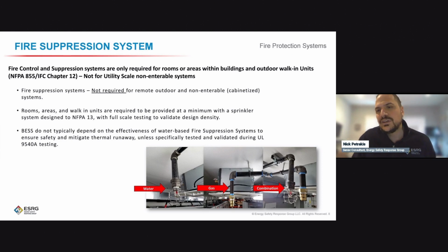Fire suppression systems really depend on where it's located. Indoor systems, walk-in units will require this mandatory, assuming this is in a building. Outdoor systems are more reliant on making sure that failure is contained within that enclosure and doesn't propagate, so they're not required to have external or water-based fire suppression systems. It really depends on fire testing results showing that you can contain that failure either to the initiating rack or within that enclosure, and it doesn't spread to adjacent systems and exposures.